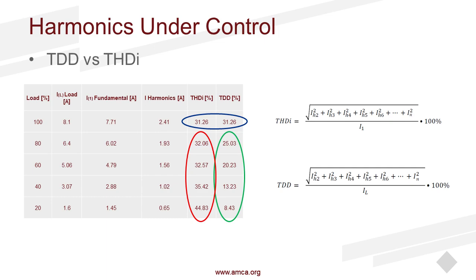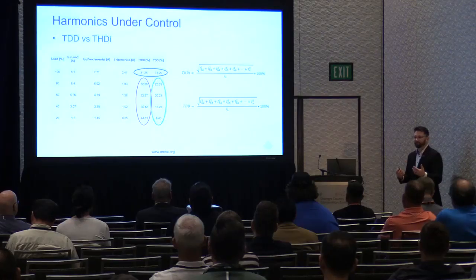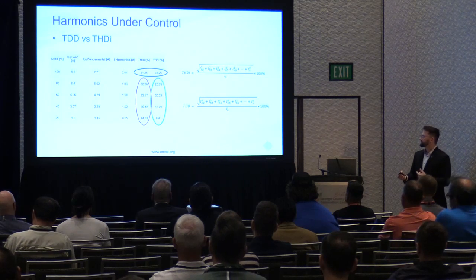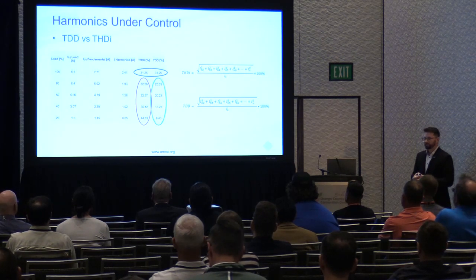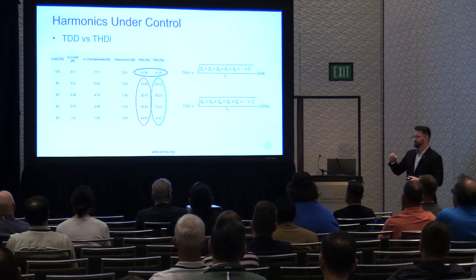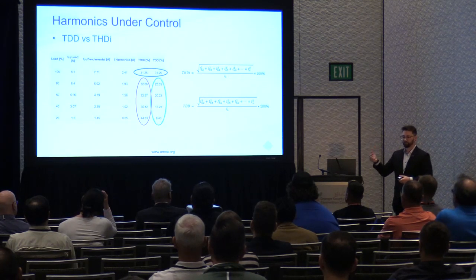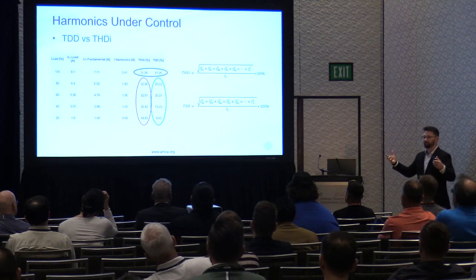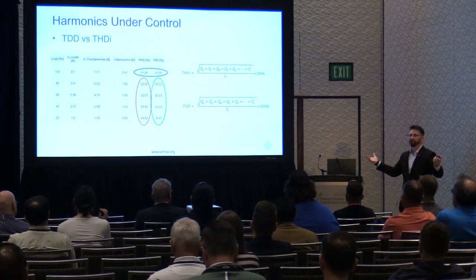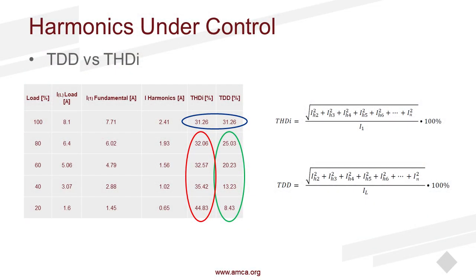This is because the ratio of current is different, right? So your total harmonic distortion current, you're seeing an increase in percentage, but that's not actually an increase of harmonic currents that you're seeing. The total demand distortion is showing how much total harmonic current you're seeing on the system, which is actually decreasing because the amount of current on your system as you lower the load is less. You have less harmonic load. But the percentages is where you're seeing the difference. Hopefully this is making sense.